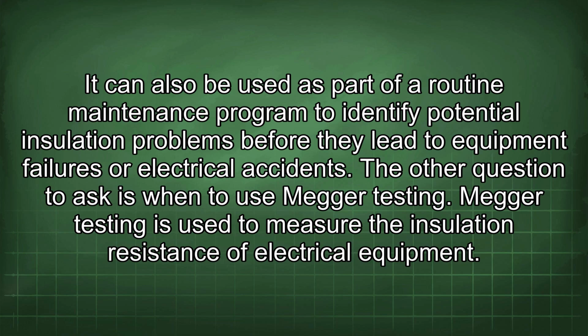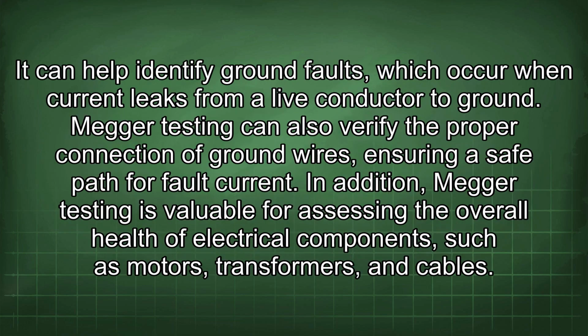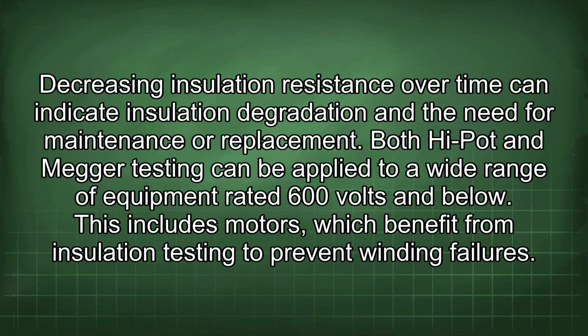The other question to ask is when to use Megger testing. Megger testing is used to measure the insulation resistance of electrical equipment. It can help identify ground faults, which occur when current leaks from a live conductor to ground. Megger testing can also verify the proper connection of ground wires, ensuring a safe path for fault current. In addition, Megger testing is valuable for assessing the overall health of electrical components such as motors, transformers, and cables. Decreasing insulation resistance over time can indicate insulation degradation and the need for maintenance or replacement.